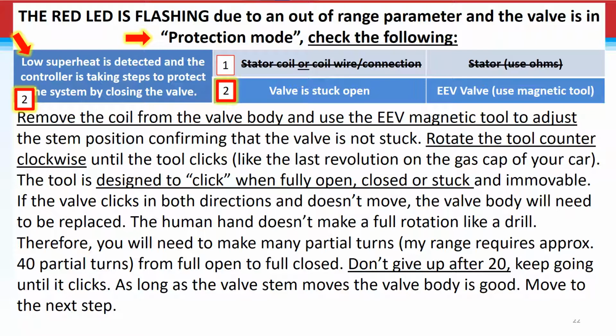Remove the coil from the valve body and use the EEV magnetic tool to adjust the stem position, confirming that the valve is not stuck. Rotate the tool counterclockwise until the tool clicks like the last revolution on the gas cap of your car. The tool is designed to click when fully open, fully closed, or if it's stuck and immovable. If the valve clicks in both directions and doesn't move, the valve body will need to be replaced.